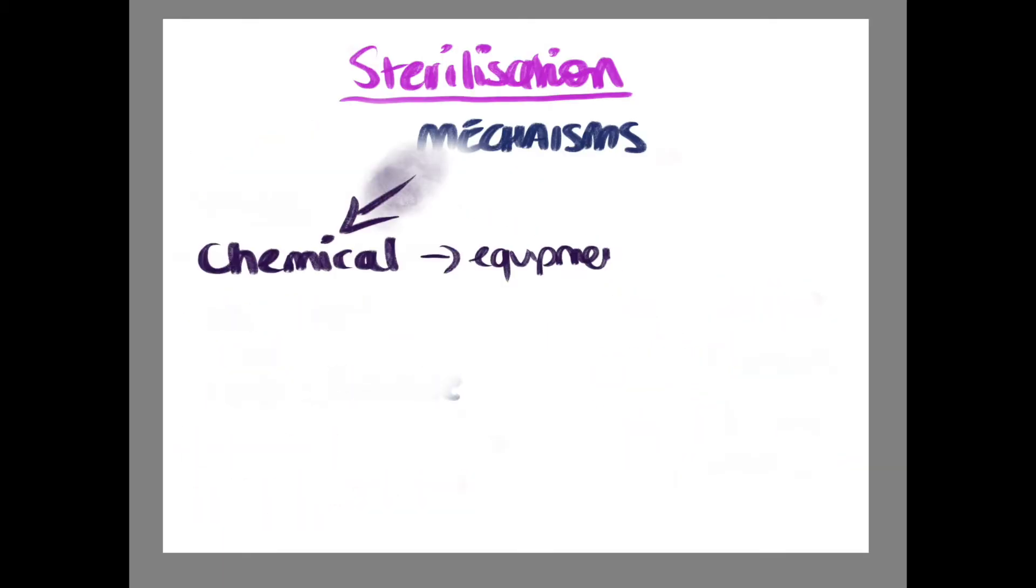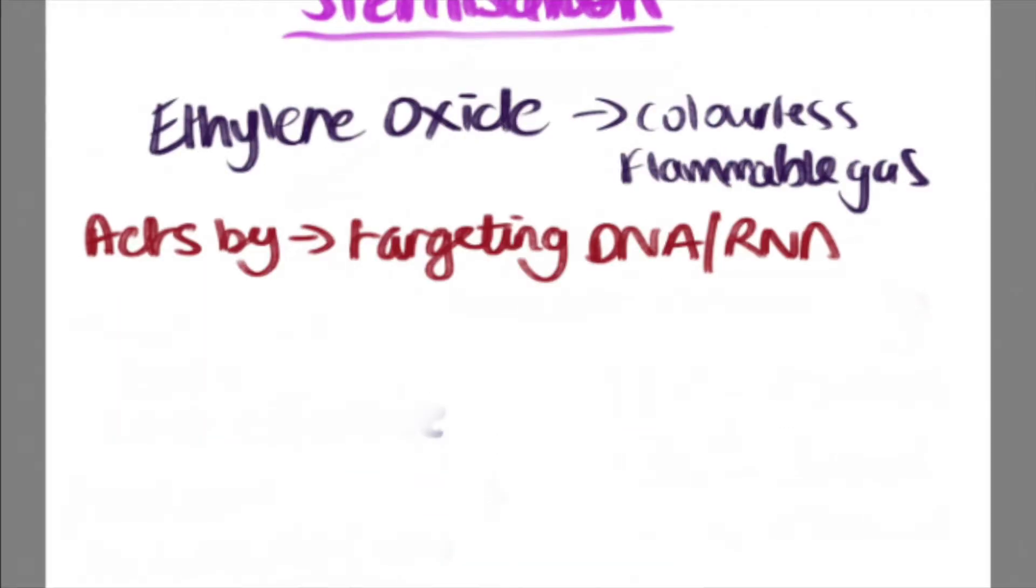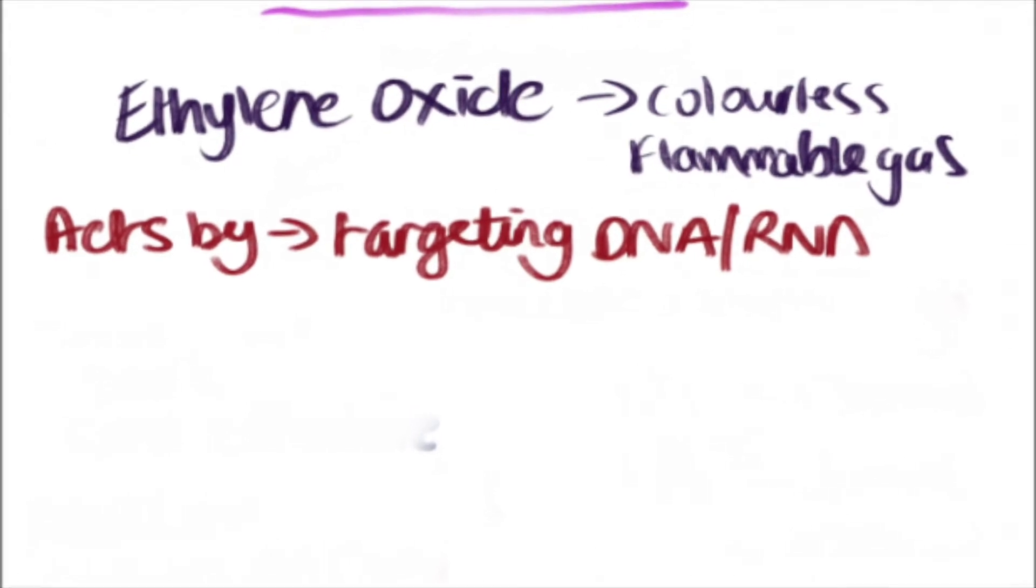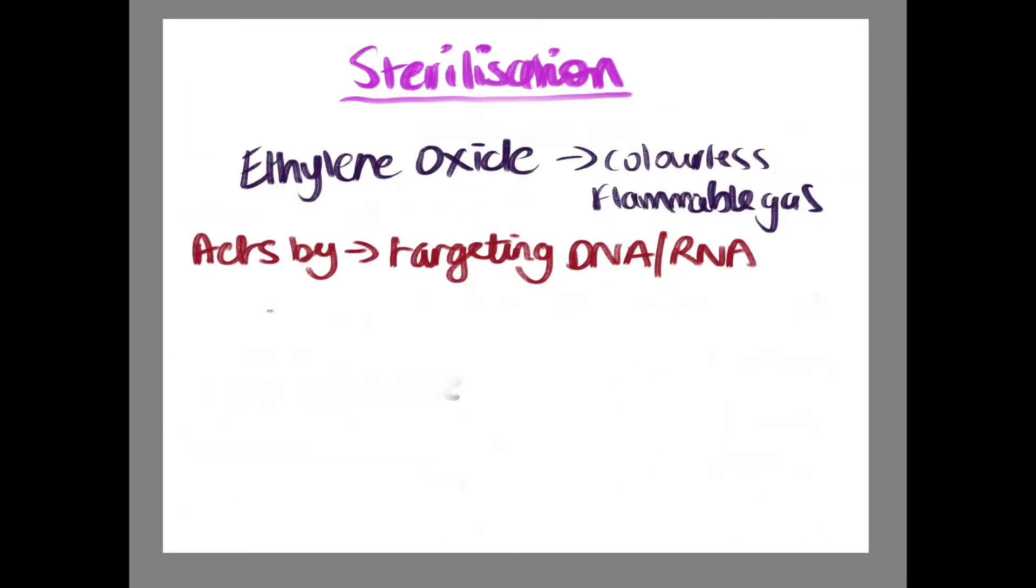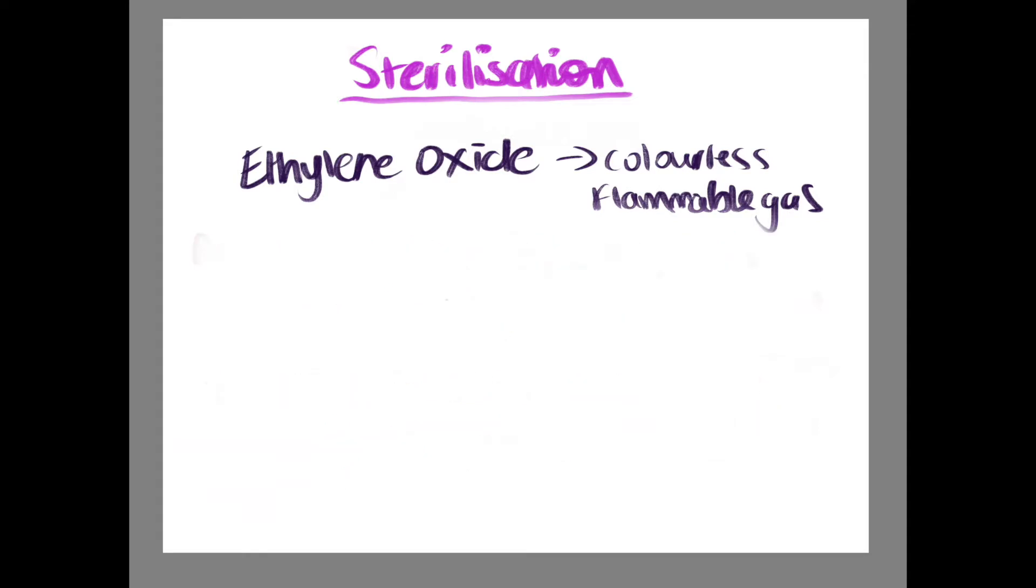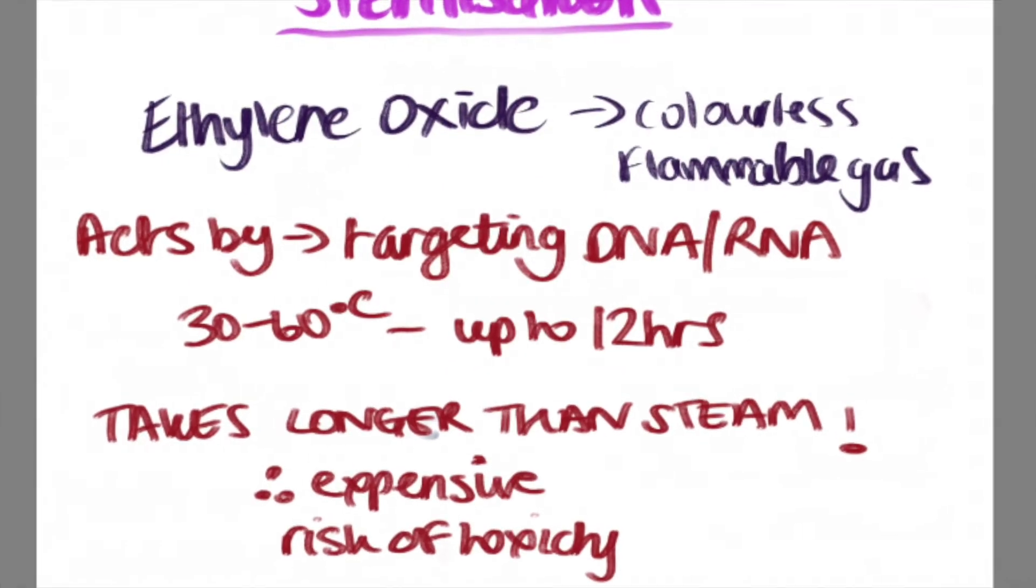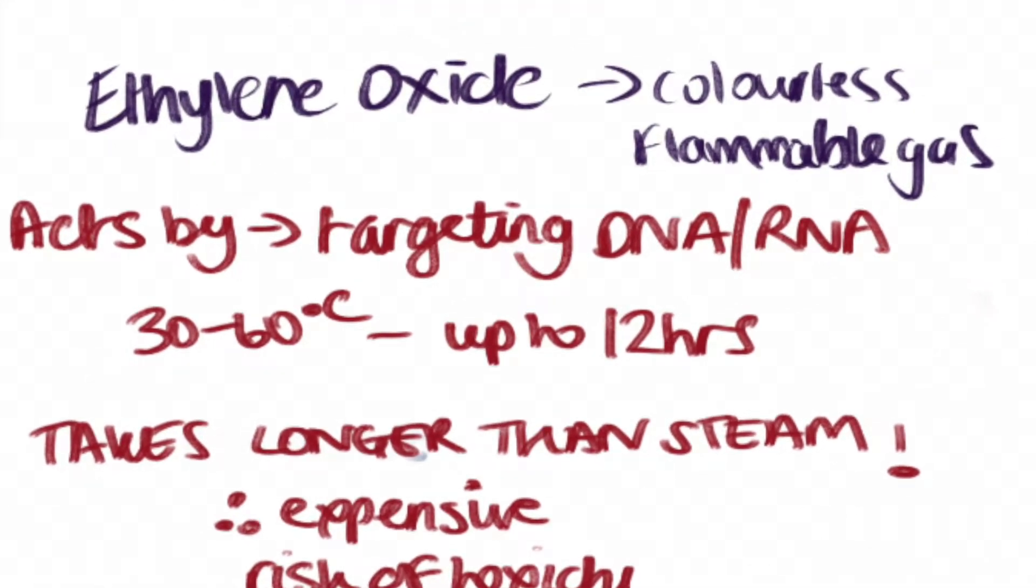Chemical sterilization: If the equipment cannot tolerate steam, then this is the next best thing. Ethylene oxide is a colorless and flammable gas which causes antimicrobial activity by targeting protein, DNA and RNA. Temperatures of around 30 to 60 degrees Celsius are used in cycles lasting up to about 12 hours. Despite not needing high temperatures, the duration of sterilization is longer than steam. There is a risk of toxicity and currently, respiratory equipment is not recommended to be sterilized via this process. It is a relatively expensive and resource intensive process.